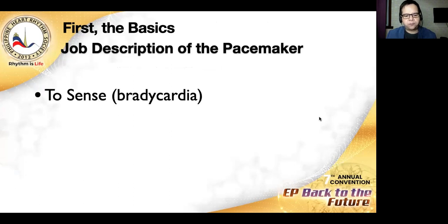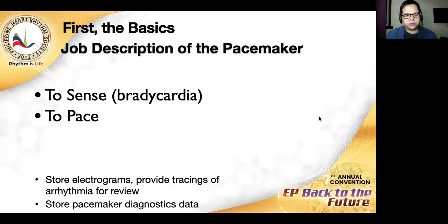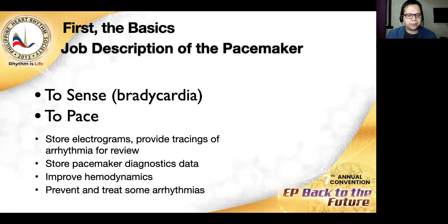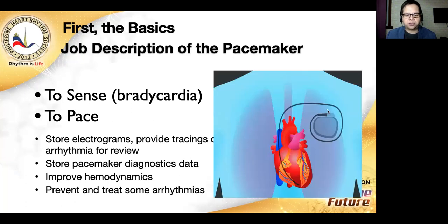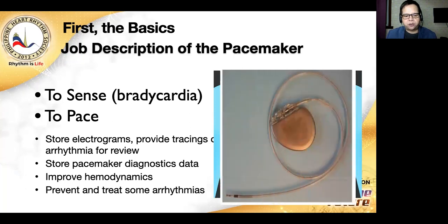The job description of the pacemaker is basically to sense bradycardia, and if it senses bradycardia, it will pace. It does this continuously, repeatedly, all throughout its battery lifespan, along with other functions such as storing data. The pacemaker system consists of the pulse generator implanted in the pectoral area, which contains the battery, and the lead, which is implanted into the cardiac chambers. This is a clearer, real-time picture of the device set, with the lead and the electrode at the tip connected to the pulse generator.